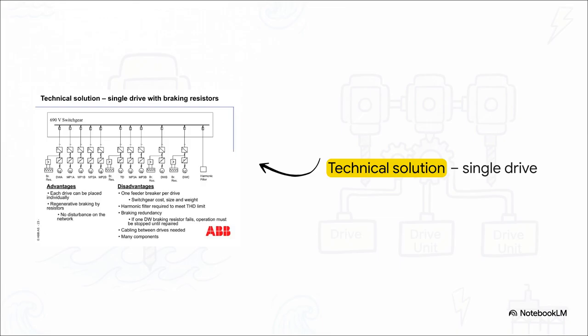Let's see how this actually plays out in a single drive schematic. Picture your 690-volt switchgear. For every single motor you're running, whether that's a drawworks, a top drive, maybe a mud pump, the single drive layout demands a full rated supply breaker and a dedicated rectifier section. So if you've got 10 drives, well, you're going to have 10 separate feeder breakers lined right up. As you can imagine, that completely eats up your available switchgear space.